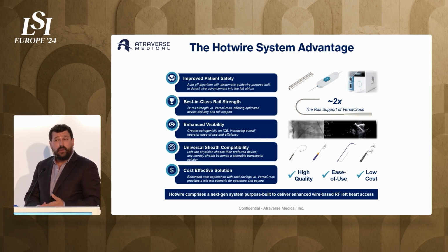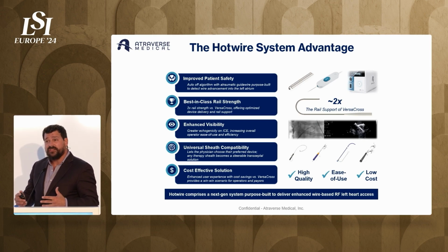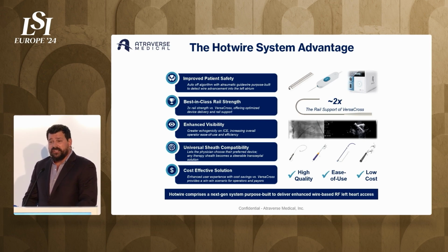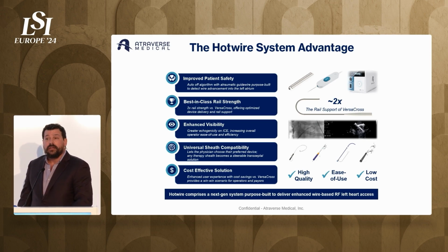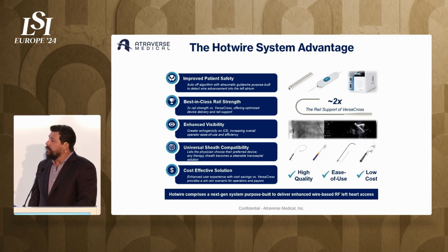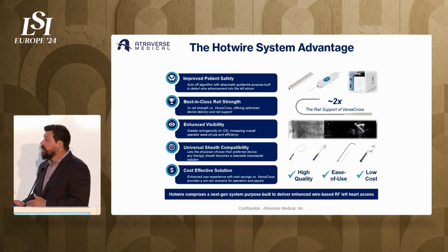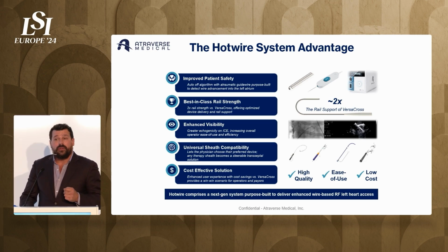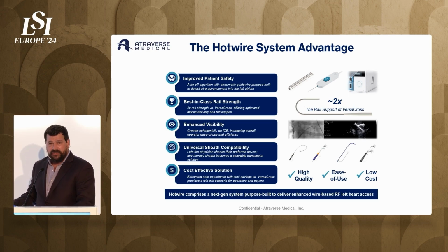Additionally, our wire is actually twice as rigid as a rail, which is important in the advent of increasingly large bore sheaths. It's another way of saying it's easier to advance these larger sheaths over the wire relative to the VersaCross device. Also importantly, in the U.S., intracardiac echo, or ICE, is how the physicians see where they're at and what they're doing. And our device, as the coils go all the way down to the distal tip, is much easier to see on ICE. Furthermore, I mentioned the universal sheath compatibility.